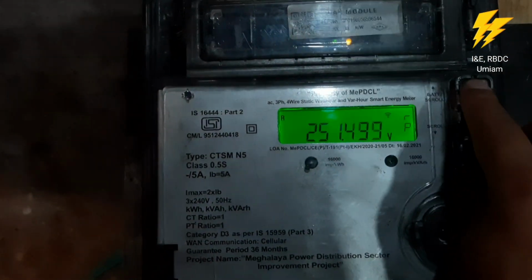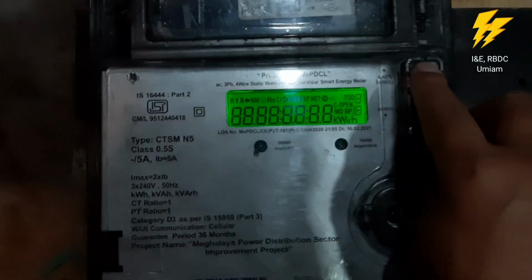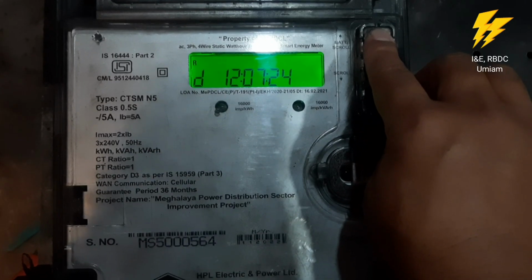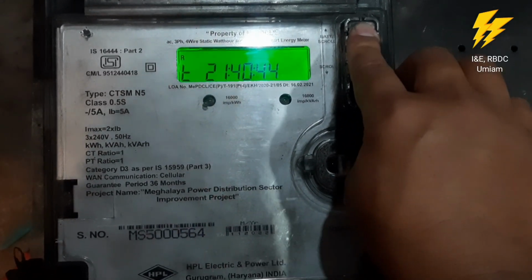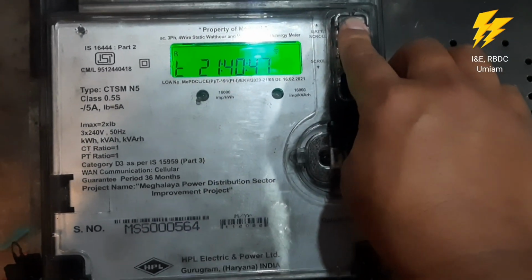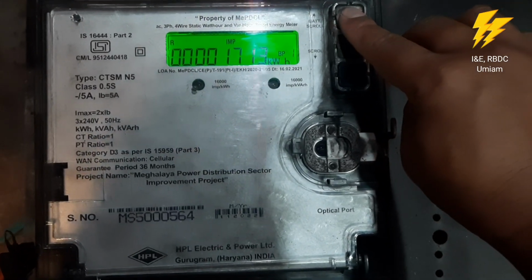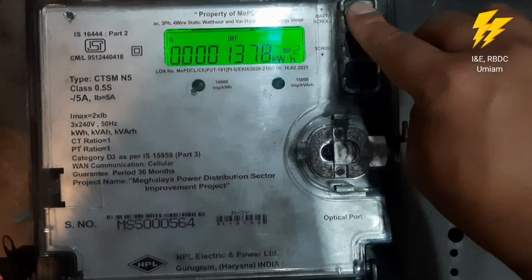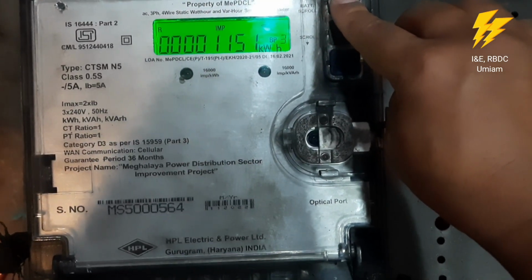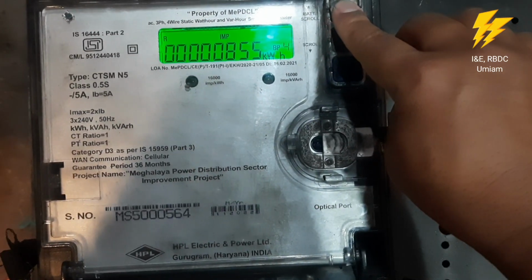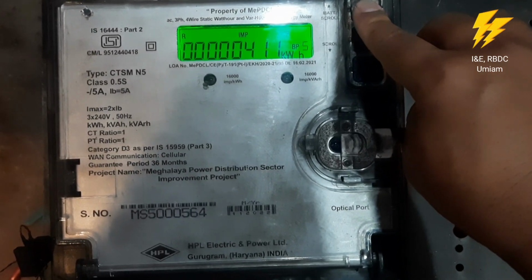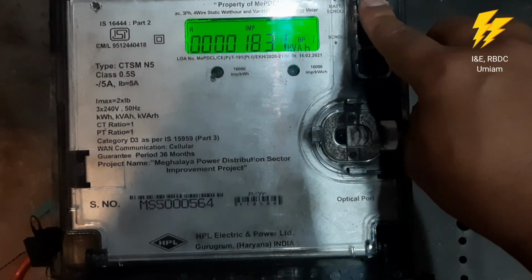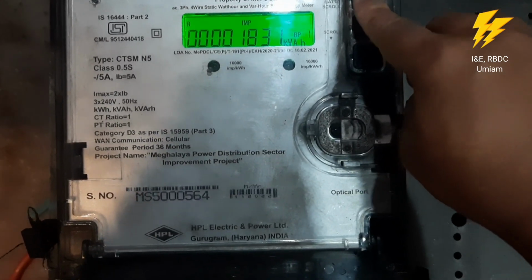And then we'll go to the push button mode. We normally go to push button mode when we have to see the demand, because sometimes if billing of the consumer is done on manual basis, then we have to check for any excess load, and as per the Electricity Act there will be a penalty if you exceed your connected load, and because of that you have to see what is the demand. That is important. Otherwise, for small consumers, you don't have to look at all these nitty-gritty of penalizing them.